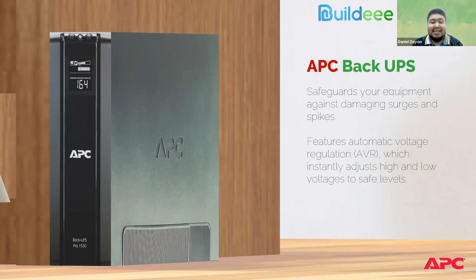By the way, DJ mentioned earlier that he has an air purifier. Those are devices we do not allow on our UPS. Just a tip, because you might think all devices can be plugged into the UPS. That is a big no, because what we plug into our UPSs are our IT equipment: desktops, routers or modems, the NVR, or CCTV cameras. Anything with refrigerant, motors inside, or heating parts is not allowed on a UPS. Just a tip for those who would like to invest in a UPS.